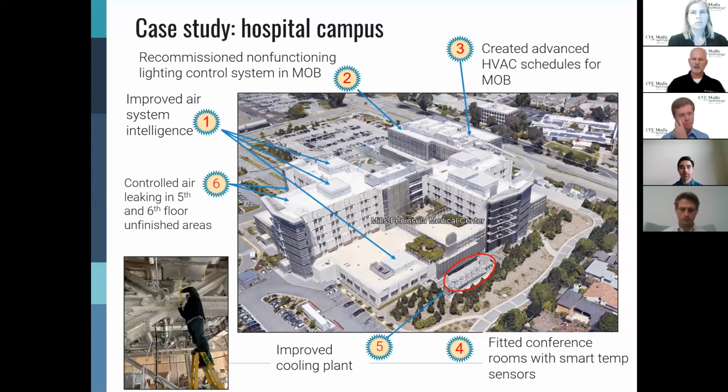So again, connecting this space between, right, connecting design to the building automation, and then overlaying a strategy on top of that, and then staying with the vision. And again, we were able to make a huge impact, a 30% reduction in energy use for that chilled water central plant by implementing what we did.